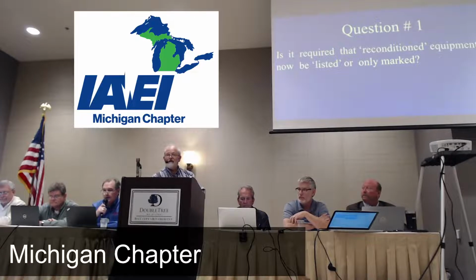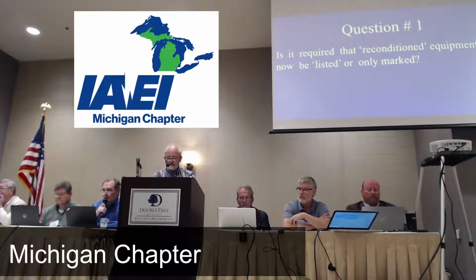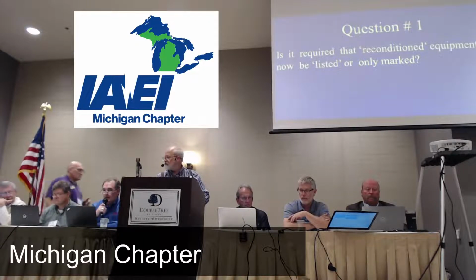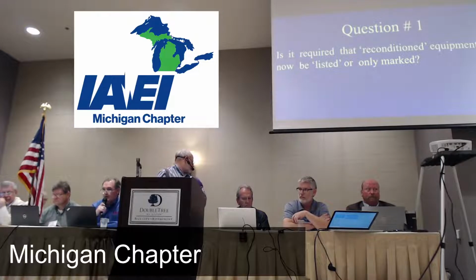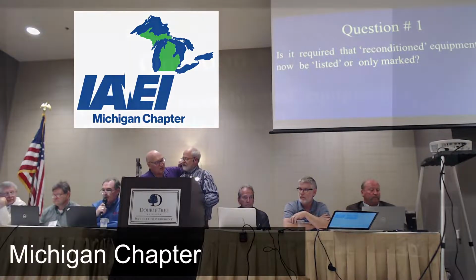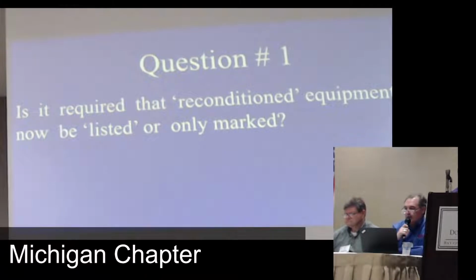The requirements in the NEC, section 110.21(A)(2): reconditioned equipment shall be marked with the name, trademark, or other descriptive marking by which the organization responsible for reconditioning the electrical equipment can be identified, along with the date of the reconditioning. Reconditioned equipment shall be identified as reconditioned, and the original listing mark shall be removed, so nobody sees the original listing mark and thinks, oh, it's good to go. Approval of the reconditioned equipment shall not be based solely on the equipment's original listing.